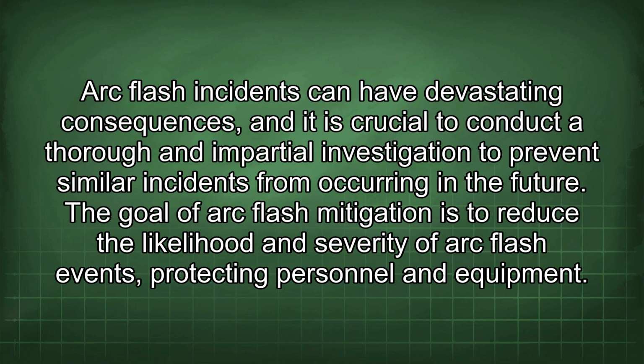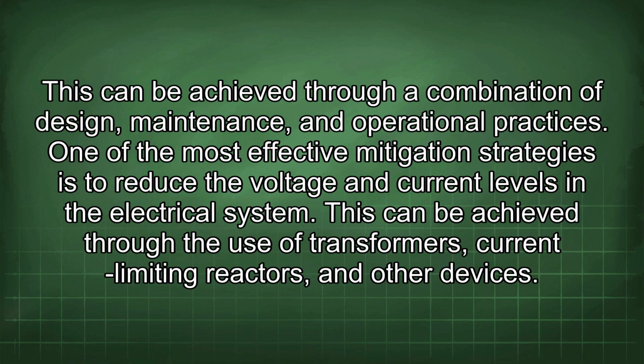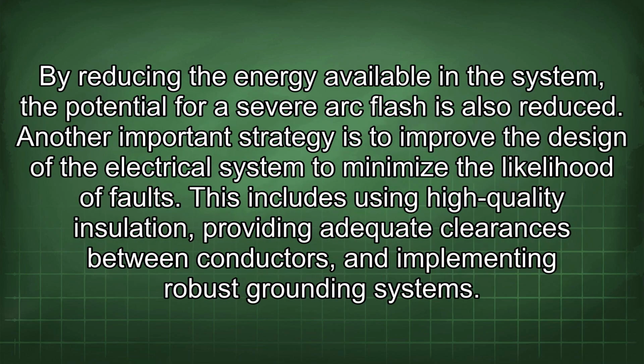The goal of arc flash mitigation is to reduce the likelihood and severity of arc flash events, protecting personnel and equipment. This can be achieved through a combination of design, maintenance, and operational practices. One of the most effective mitigation strategies is to reduce the voltage and current levels in the electrical system. This can be achieved through the use of transformers, current-limiting reactors, and other devices. By reducing the energy available in the system, the potential for a severe arc flash is also reduced.